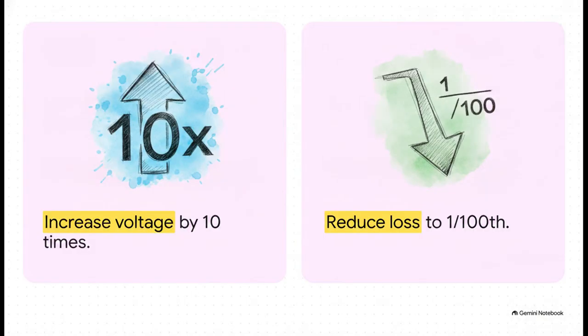This illustrates what we can call the 100x rule. If we increase the voltage by a factor of 10, the current drops to just 1/10 of what it was. But because of that squared relationship, your power loss drops to 1/100th. A mere 10 times increase in voltage slashes your energy waste by a factor of 100. That's an incredible return on investment from a pure physics standpoint.